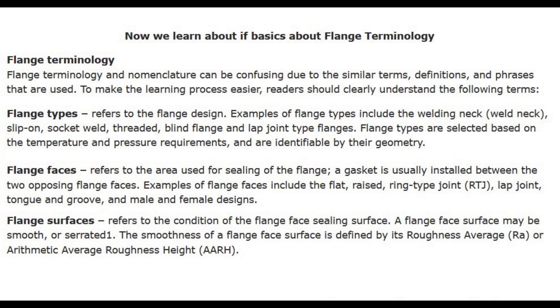Flange faces refers to the area used for sealing of the flange. A gasket is usually installed between the two opposing flange faces. Examples of flange faces include the flat, raised, ring-type joint (RTJ), lap joint, tongue and groove, and male and female designs. Flange surfaces refers to the condition of the flange face sealing surface; a flange face surface may be smooth or serrated. The smoothness of a flange face surface is defined by its roughness average (RA) or arithmetic average roughness height (AARH).